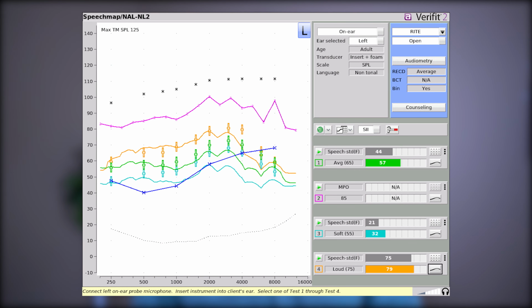Remember earlier when I ran the Real Ear Measures test, I'll put another image here on the screen of the results. The output curves are not matching the targets, and best practice, the gold standard of hearing care, is within a few months after the fitting to give you the best hearing possible is to match those curves to those targets. There is a risk of underfitting. That means you may miss 10, 15, 20% of what's possible in terms of better hearing with these hearing aids.